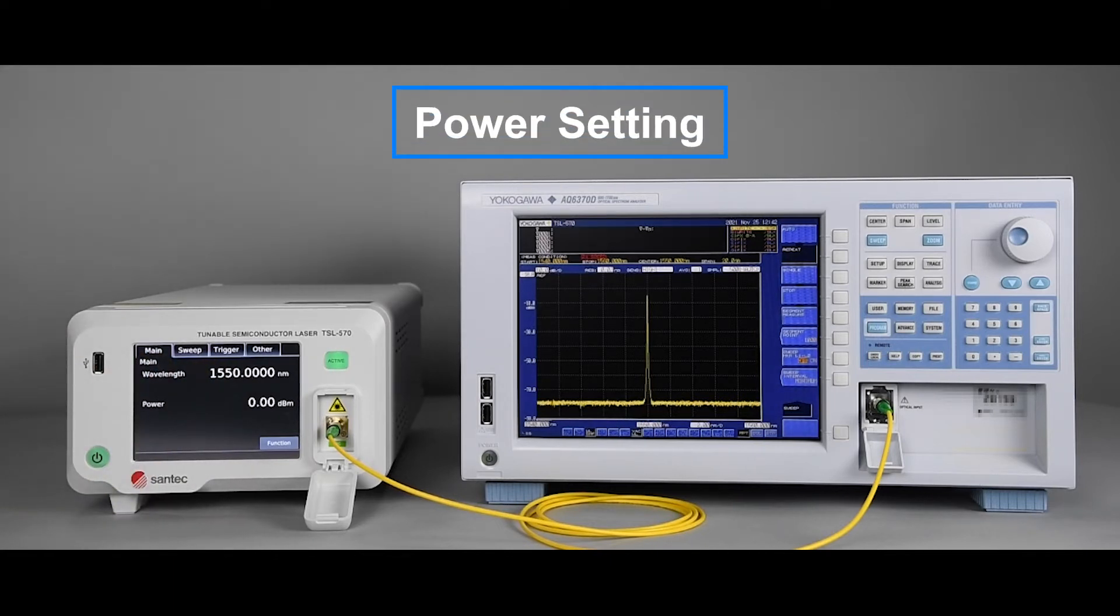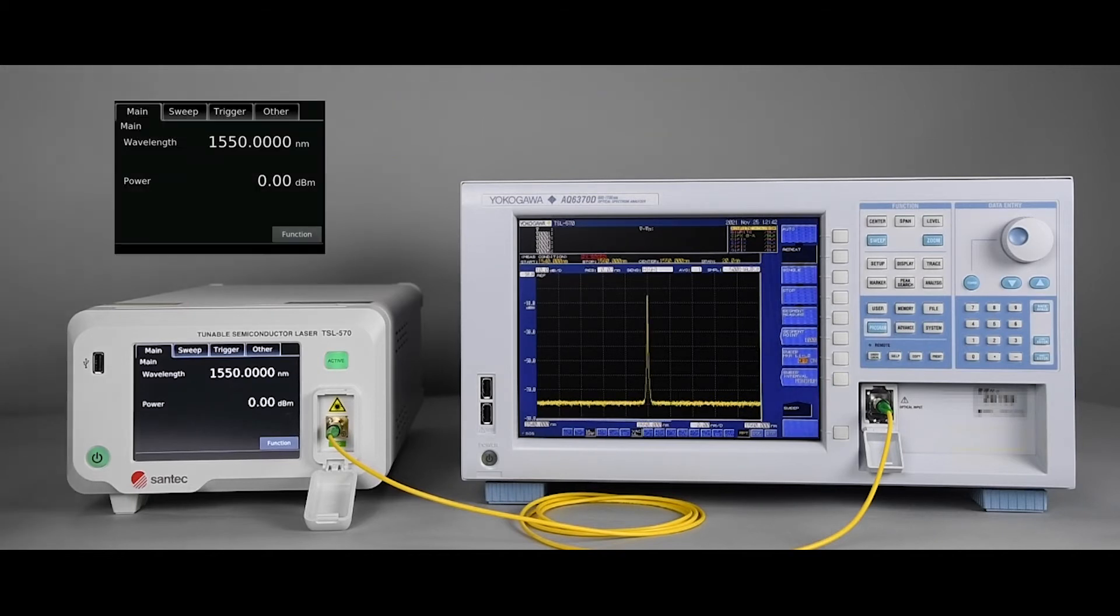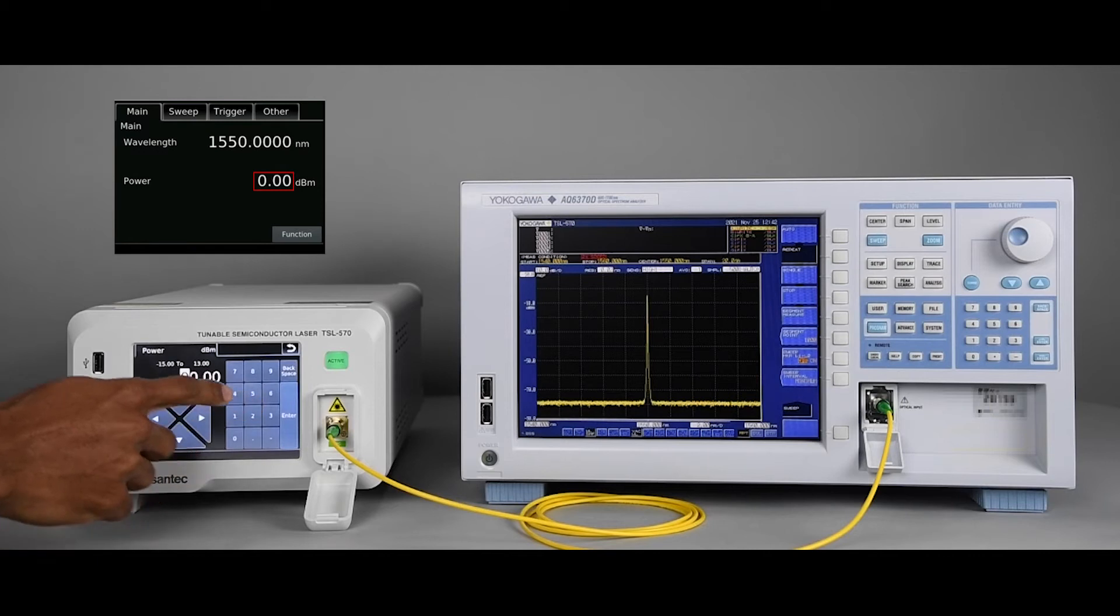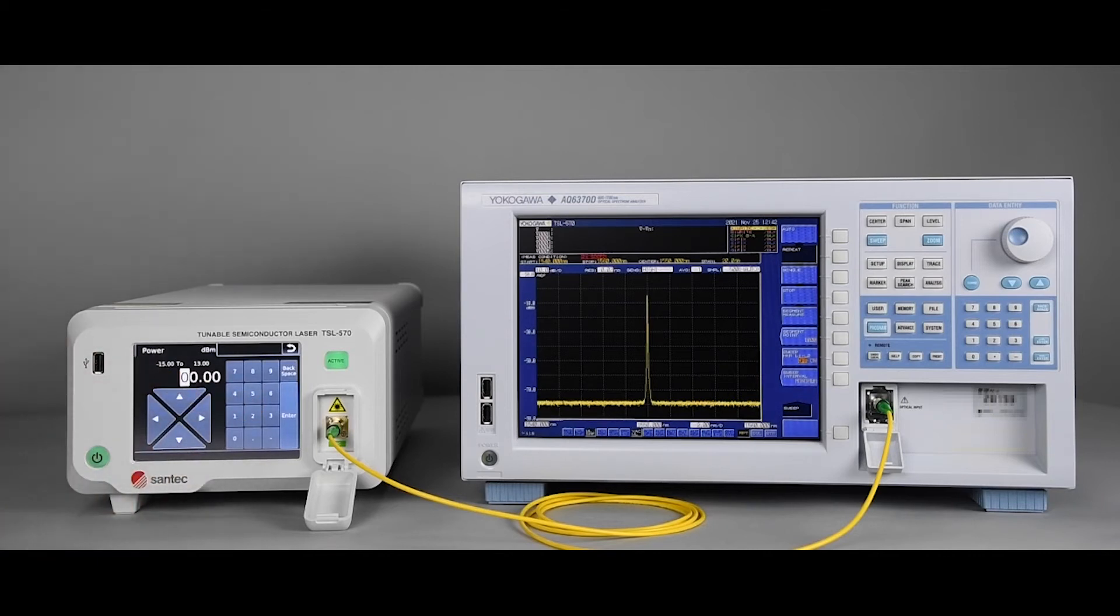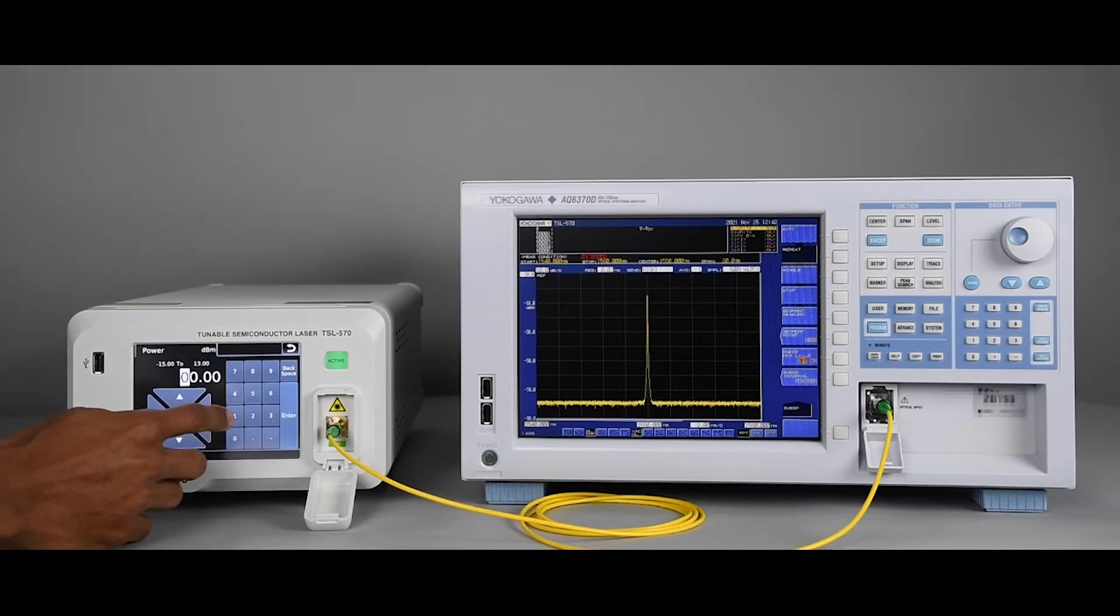Next, let's modify the TSL's output power. Similar to changing the wavelength, just tap on the power value. The display will switch to the keypad screen where the power value can be entered. Let's set it to 10 dB and press Enter.